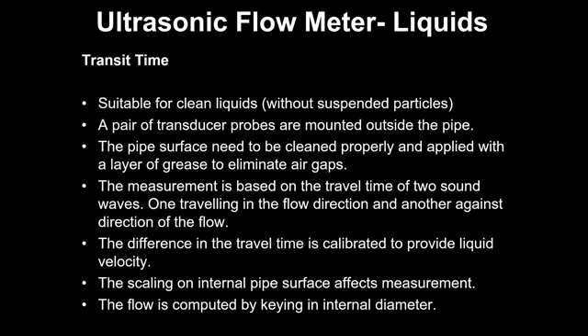The diameter has to be keyed in, so we have to key in the diameter properly. If the diameter is wrong, the flow is going to be wrong, obviously, because the flow is proportional to the square of the diameter. So the error in diameter will get magnified.